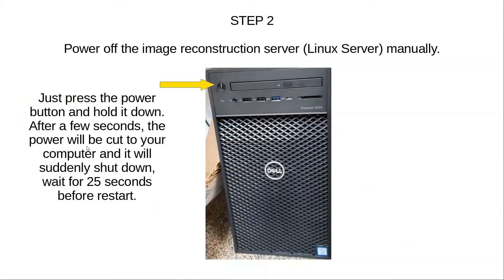In step 2, you need to power off the image reconstruction Linux server. To do this, press the power button for a few seconds and then release it. You have to do it manually because this Linux server is headless, meaning it is not connected to any keyboard, mouse, or monitor.